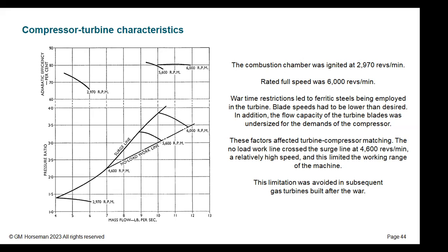approached the surge line at about 4,600 revs per minute. So that limited the range of operation. Two things contributed to that. One was the fact that carbon half moly was used for the rotors, which limited the dimensions of the machine, so it didn't have freedom to design what they wanted. But also Parsons made a mistake to a degree in matching compressor and turbine. So we learned the lesson, and that was put right on the next machines that were built.